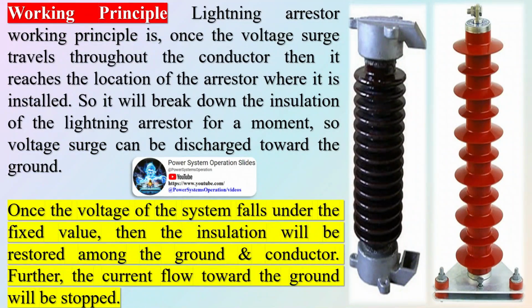Strikes come in two types: direct and indirect. A direct strike can immediately cause a fire in the system, and an indirect strike can induce a large amount of voltage as discussed earlier. In other words, a lightning arrestor diverts the abnormal high voltage to the ground without affecting the continuity of supply. It is connected between the line and earth, i.e., in parallel with the equipment to be protected at the substation.